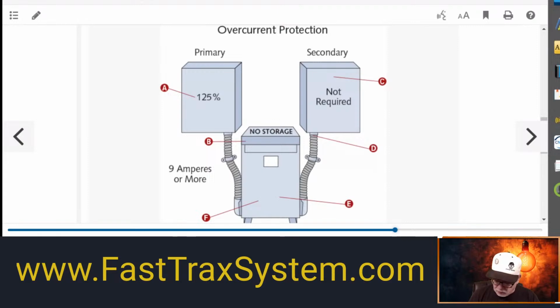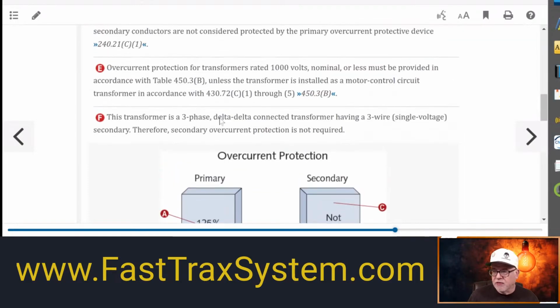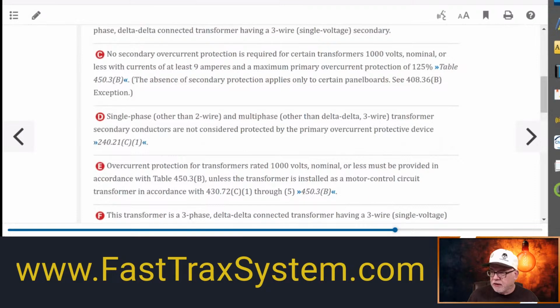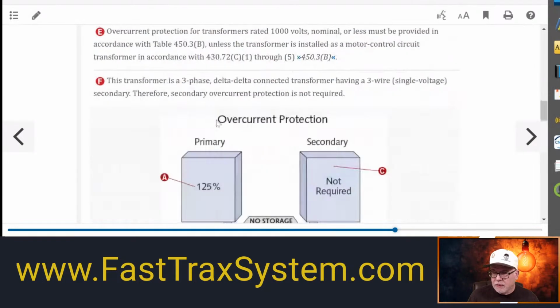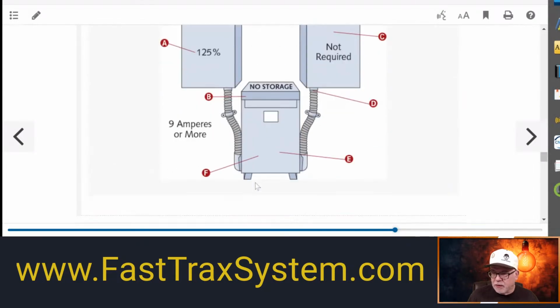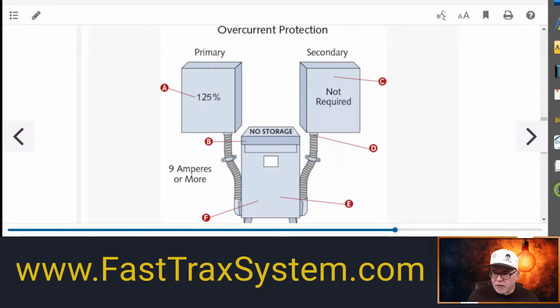All right, so in this case, if it was 90.21, the maximum primary protection at 125% would be, let's do the math. That would be 90.21. Again, you can drop the 0.21 if you wish, times 1.25. And that's going to be 112.76. So it'll be 112.76. So in our case here, let's talk about the primary. That would be our primary protection.